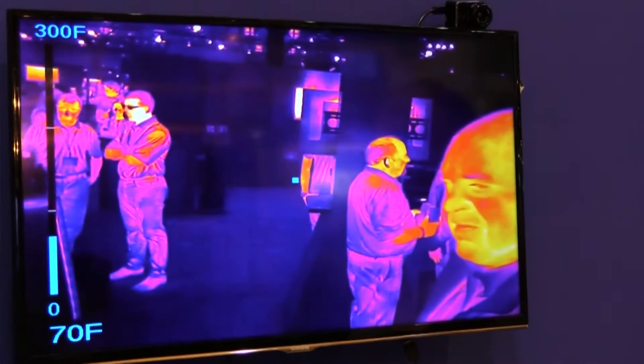So what exactly is radiometry for those who aren't familiar? In the infrared world, that means measuring temperature accurately. But don't all thermal cameras measure temperature? They all detect temperature, but they don't all measure it accurately. The infrared detectors are great thermal sensors but they don't give you an accurate measure of an exact temperature. So now by looking at something from the air you can know precisely how warm it is.